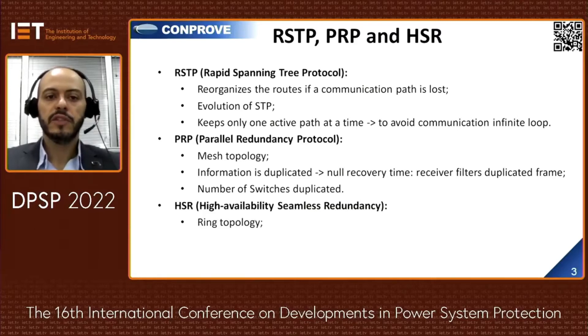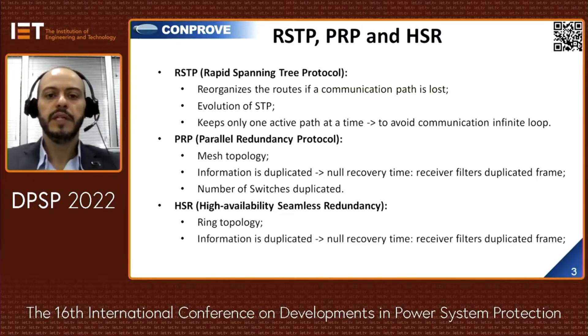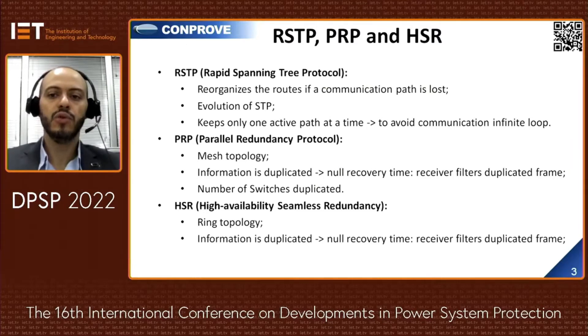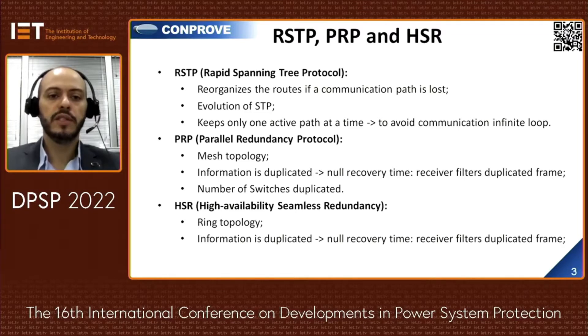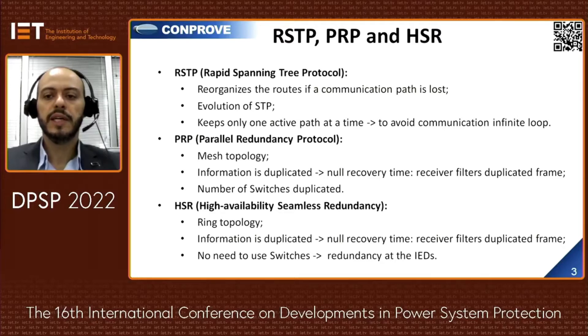The HSR, High Availability Seamless Redundancy, is implemented in a ring topology. As in PRP, the information is also duplicated and the recovery time is also zero in case of link loss. A source node sends the duplicated information in both directions and the receiving nodes discard the duplicate one. In HSR, there is no need to use switches, so the redundancy is implemented at the IEDs that make up the network.